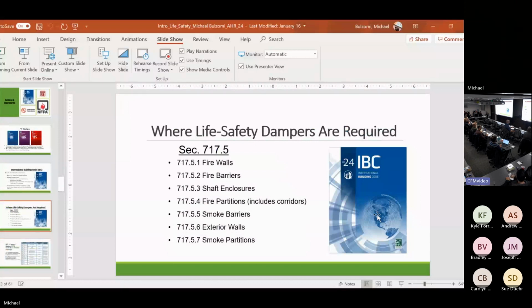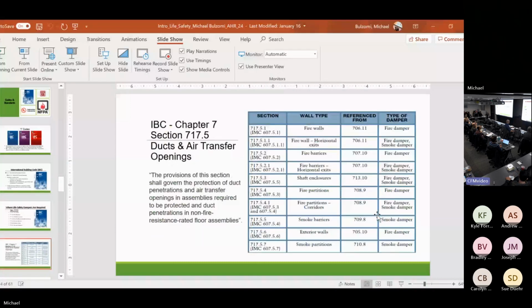Different types of barriers found in the IBC. I've got this little chart. I have a PDF of this. You'll all get a copy of it. I'll send it to CFM. Basically, it's a little cheat sheet. It tells you the wall type, what section of the code it's referenced from, and the type of damper that's required. If you see fire damper, smoke damper, again, it goes back to before the inception of combination fire smoke dampers. You had two dampers, so if you see that, that would be a combination fire smoke.